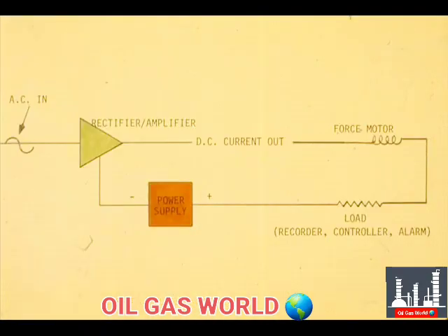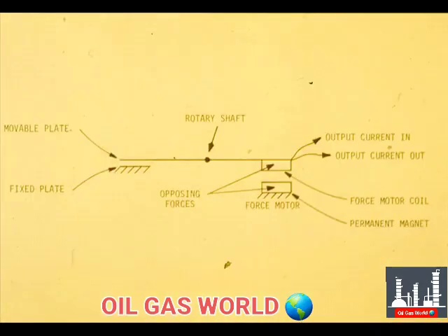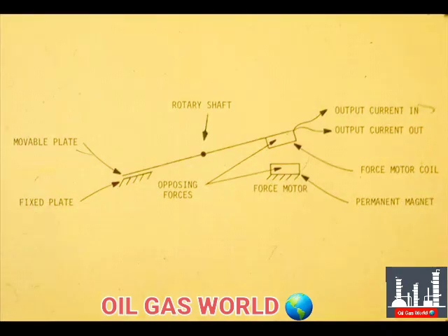The DC output current goes through a force motor and the load. The load includes the various loop items. The output current returns to the power supply. The output current passes through the force motor. The force motor coil is actually an electromagnet. Notice that the electromagnet and permanent magnet oppose each other. Increased current in the force motor causes the right end of the beam to rise and the left end to lower. The force motor supplies negative feedback.